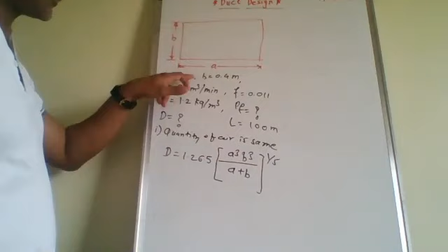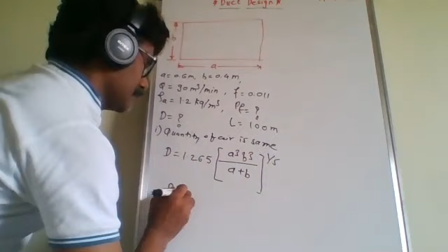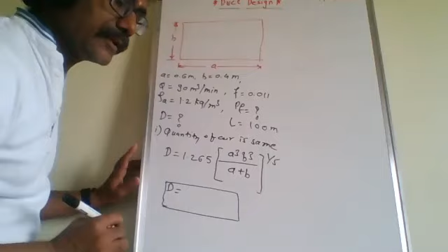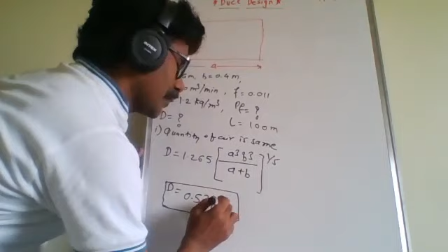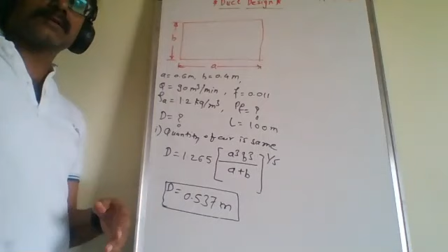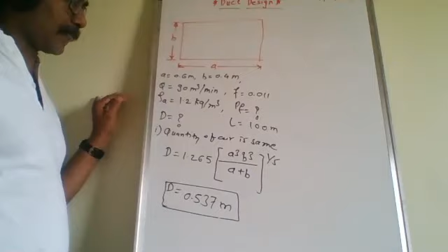So first thing is very easy. A and B both dimensions are given to us. Longer side of the rectangular duct, shorter side of the rectangular duct, both are given. So just put the numbers here and get the equivalent diameter. I get around 0.537 meter.